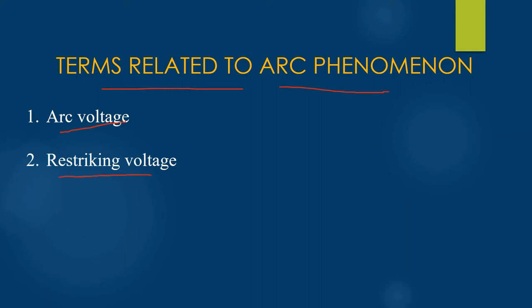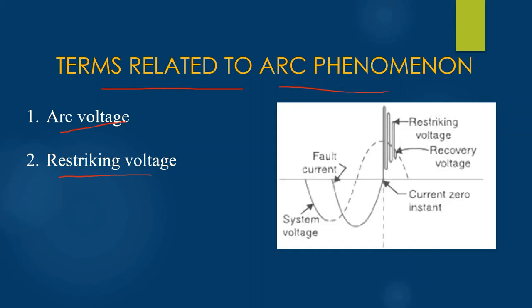Second, re-striking voltage. It is defined as the transient voltage that appears across the contacts of the circuit breaker at or near current zero during the arcing period. This is caused by the rapid distribution of energy between the magnetic and electric field associated with the plant and transmission line of the system. At the current zero situation, a high frequency transient voltage appears, and this transient voltage is known as re-striking voltage. As you can see in the diagram, these spikes are termed as the re-striking voltage — this is basically the transient voltage which is occurring during the arcing period.